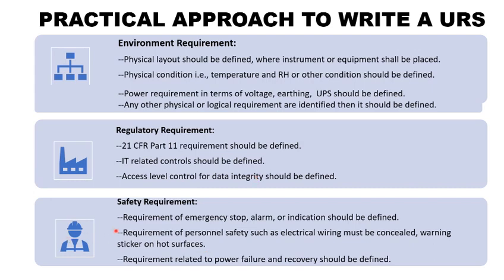Next is safety requirements. Requirements for emergency stop, alarms, or any indication should be defined. Personal safety requirements such as electrical wiring must be concealed, and warning stickers on hot surfaces should be labeled. Requirements related to power failure and power recovery should also be defined.